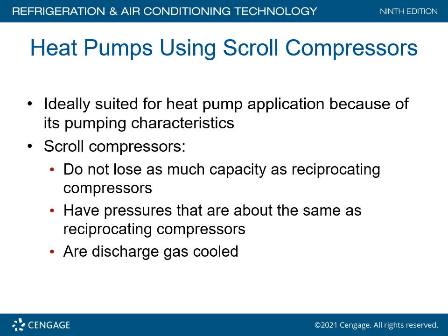Heat pumps utilizing scroll compressors, that's typically the compressor of choice today. Remember, those compressors are designed for heat pumps, not for air conditioning only. They're ideally suited for heat pump application because of their pumping characteristics. Scroll compressors do not lose as much capacity as a reciprocating compressor. They have pressures that are about the same as reciprocating compressors and are discharge gas cooled.